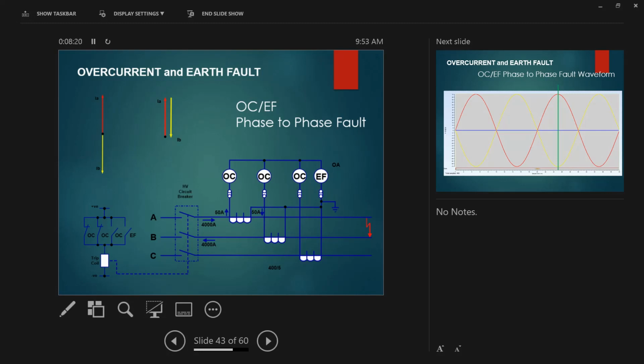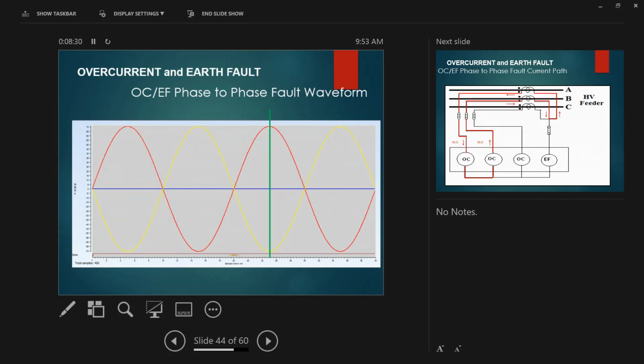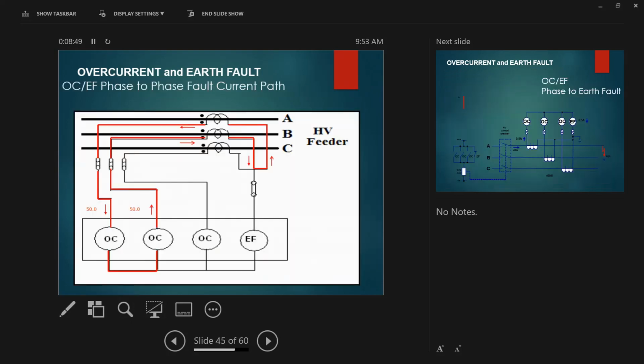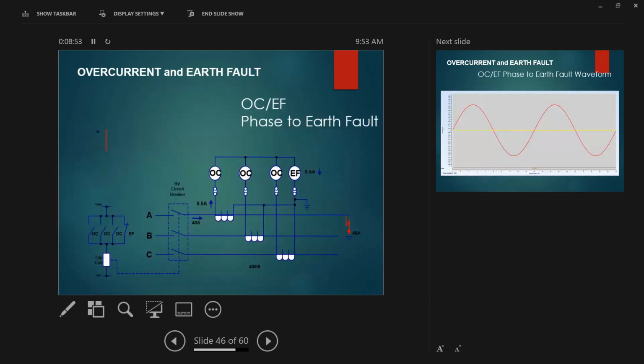So a phase to phase fault always picks up phase overcurrent or phase instantaneous, but not earth fault. So that's the behavior of a phase to phase fault. They are opposite to each other, 180 electrical degrees. So this one and this one cancel out. So your earth fault will be 0 because they just cancel out each other. That's how it goes. So there will be no earth fault flowing.